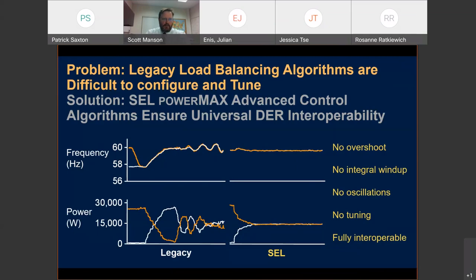And you can see as the engines were paralleled, there was some oscillation, they call it hunting in the industry. And the power oscillated until they settled down and the frequency finally settled down. That's the legacy approach, and it's really not necessary. Today we use energy packet state-based control techniques out of a relay. Relays are extraordinary load share controllers, by the way. Far more powerful than the load share controllers on your typical generator.